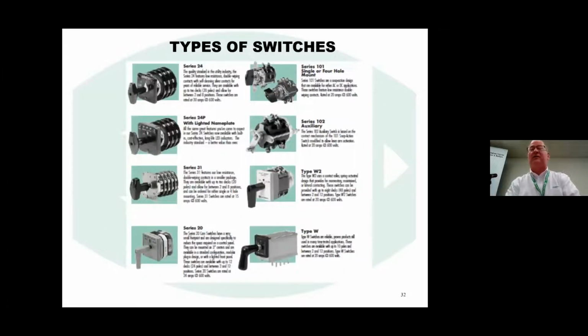That kind of summarizes my presentation for these utility style switches. Again, we've got multiple styles of other switches. In this particular picture, you can see the Series 102 auxiliary switch, and that is typically used by OEMs who put auxiliary switches on their circuit breakers. If you've seen the terminology 52A and 52B, this mechanical switch is your 52A and 52B contacts off of that breaker that is mechanically linked to the mechanical operations of your circuit breaker. So we sell literally hundreds of thousands of these switches into the OEM market for circuit breaker operation, auxiliary switch control.